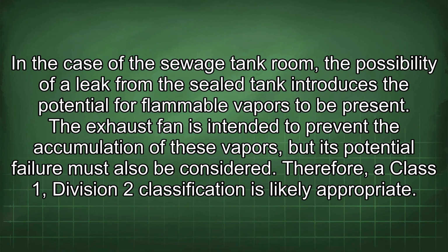In the case of the sewage tank room, the possibility of a leak from the sealed tank introduces the potential for flammable vapors to be present. The exhaust fan is intended to prevent the accumulation of these vapors, but its potential failure must also be considered. Therefore, a Class 1, Division 2 classification is likely appropriate.